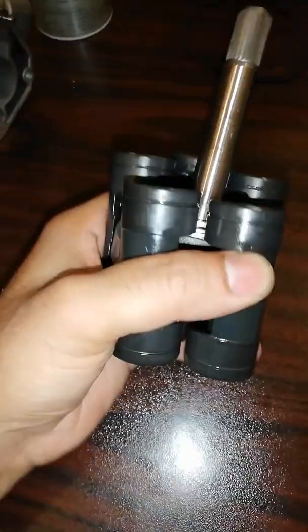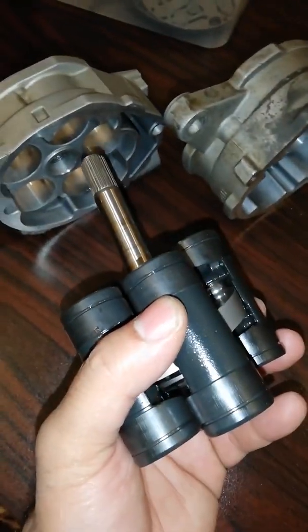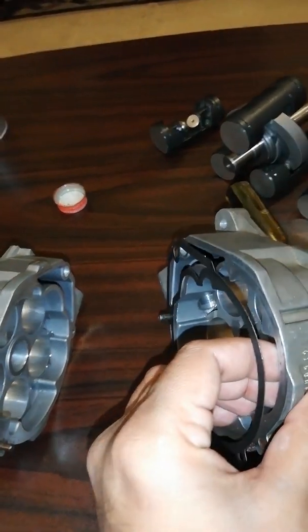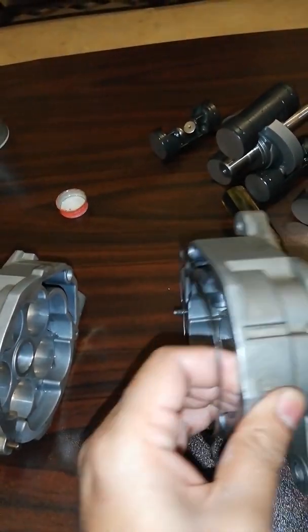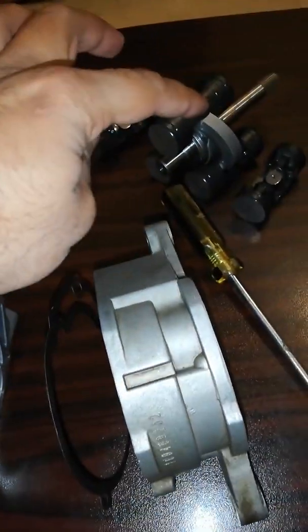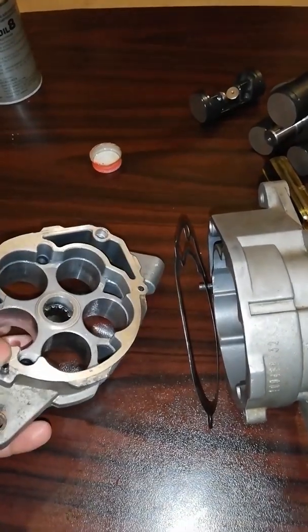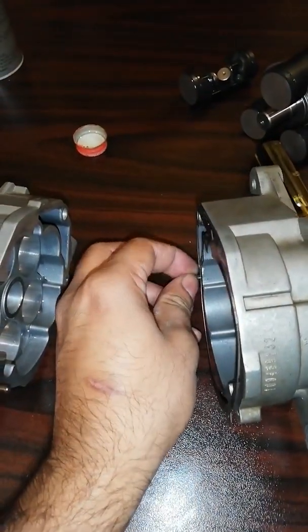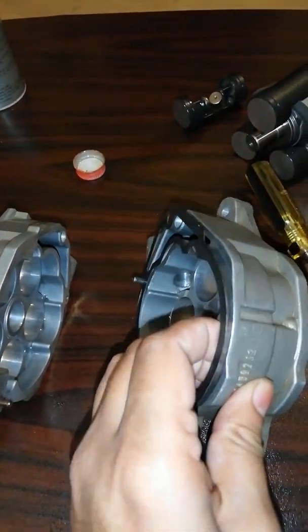The next step is placing the pistons and swash plate into the main body of the compressor. You can see these are the main body parts in which the pistons and swash plate are placed. There are two dowel pins installed on both ends of the bodies — this will reduce misalignment during fit-up.